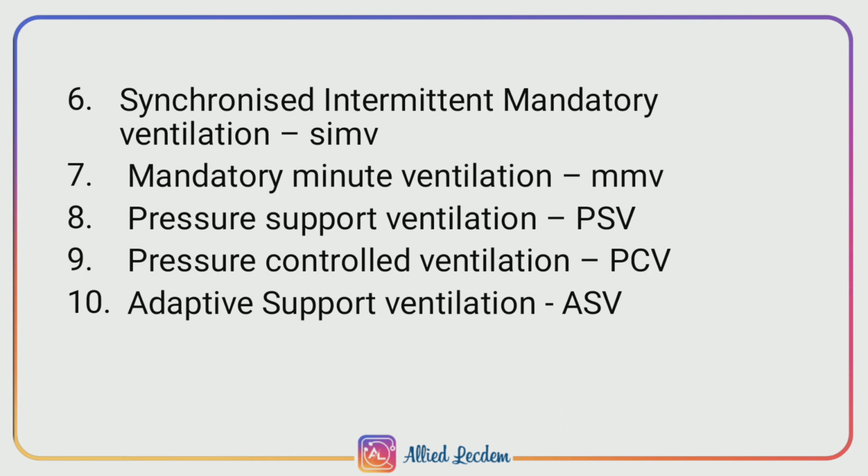Pressure support ventilation. Here, a preset pressure is delivered to each breath of the patient to attain a desired tidal volume. Pressure controlled ventilation. In PCV, the ventilator maintains a constant preset pressure for a preset time. The ventilator will cycle to expiration once the preset time has lapsed. Tidal volume is determined by set inspiratory flow and inspiratory time. Tenth one, adaptive support ventilation. The ventilator will adjust the breath automatically to the patient's requirement.